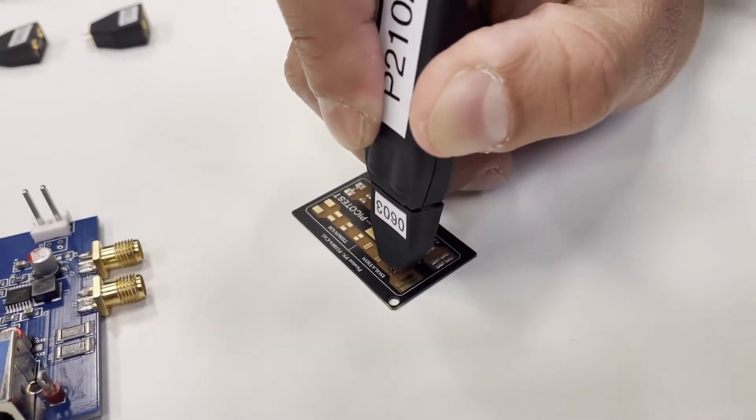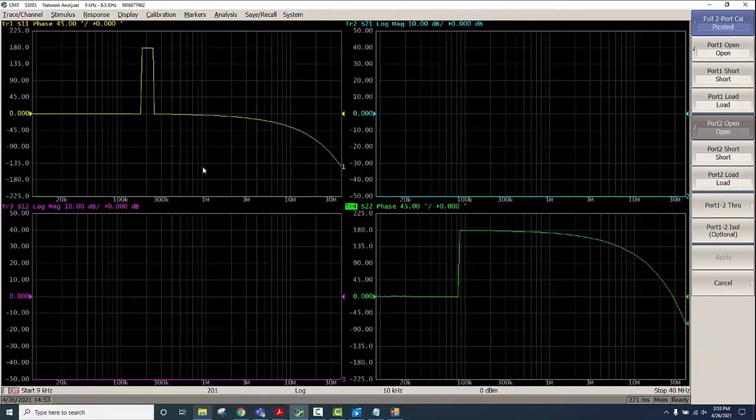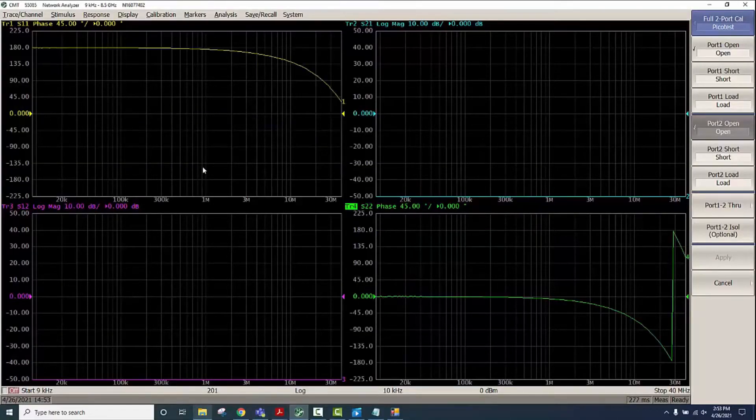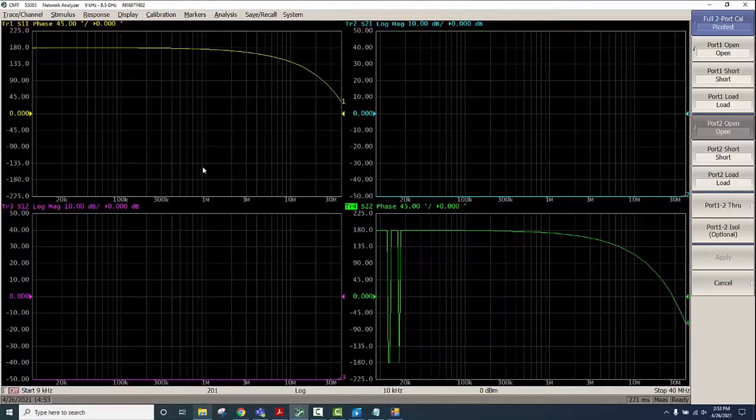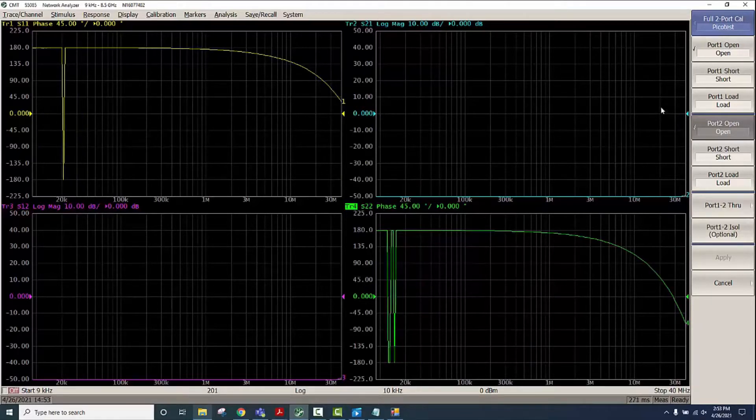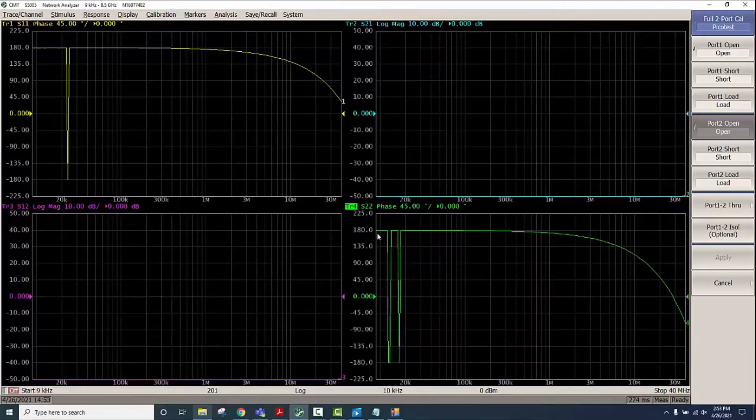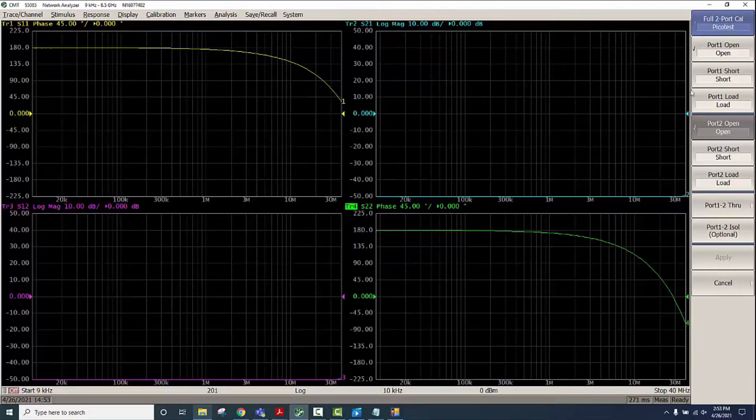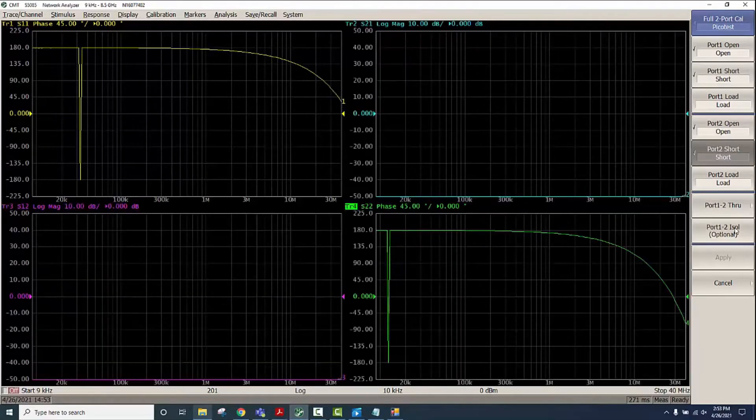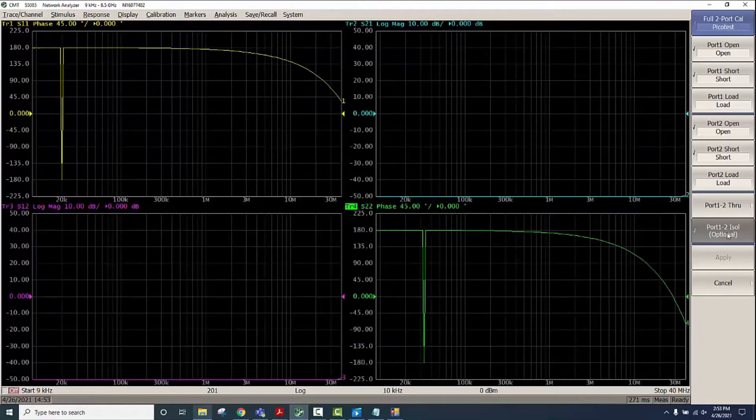This is to perform isolation as well as the short calibration. Now looking at the VNA screen we have S11 and S22 close to 180 degrees, indicating a short connection. So we'll click on Short Port 1, Port 2, as well as we'll do the isolation.